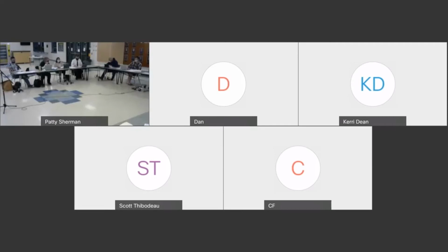I included a picture at the very end of this report of sagging ceiling tiles. It's a common problem throughout that building. Actually, the oldest wing of the building is the one that shows really the least amount of sagging from the tiles. That's caused by humidity levels not being managed, but there's also at some point a ton of fiberglass insulation just got thrown up above the grid. The grid's not rated for that. Your tiles aren't rated for that weight. So insulating is important, but doing it right is also important.